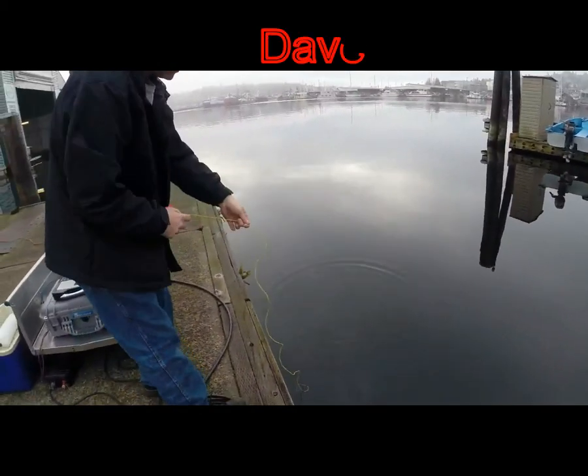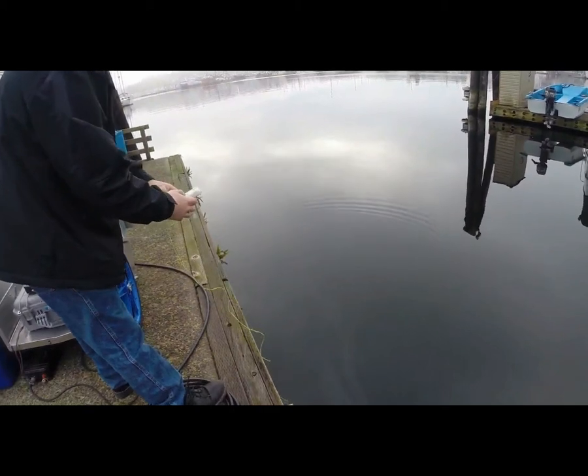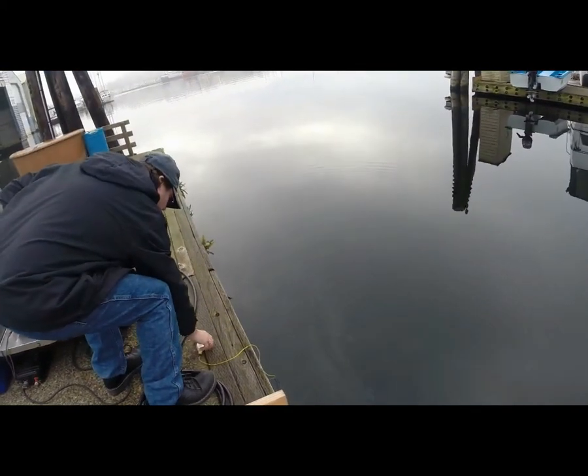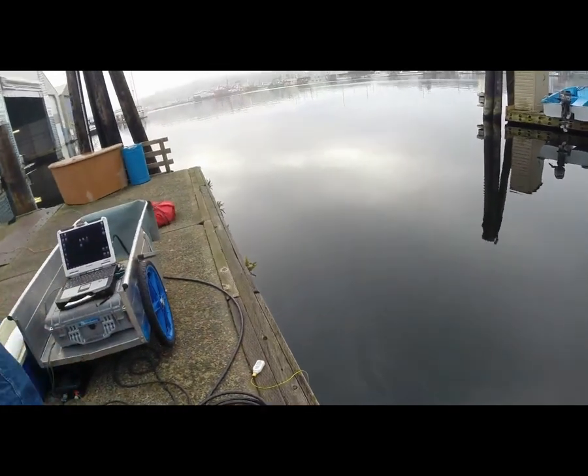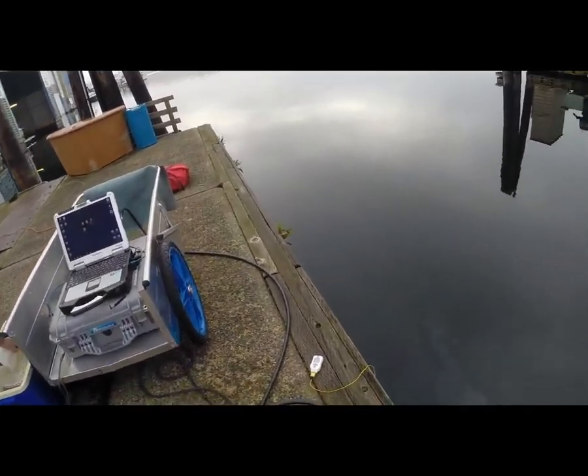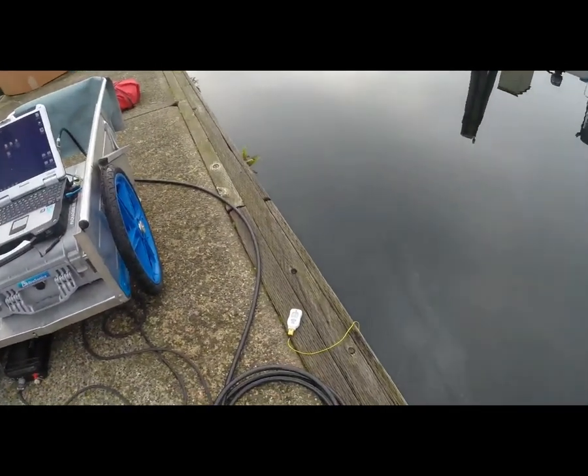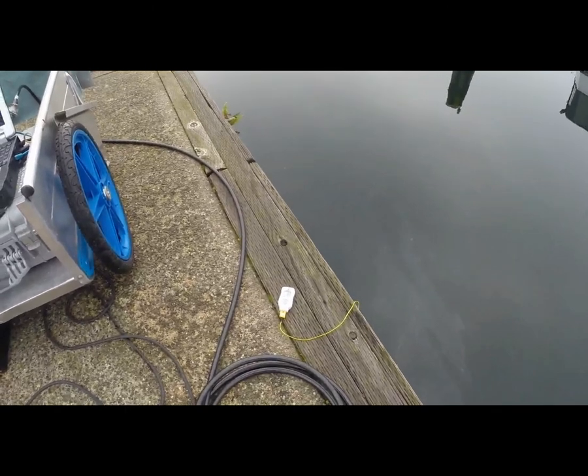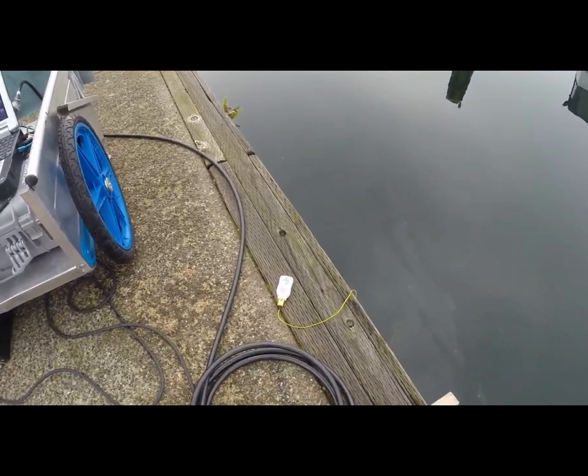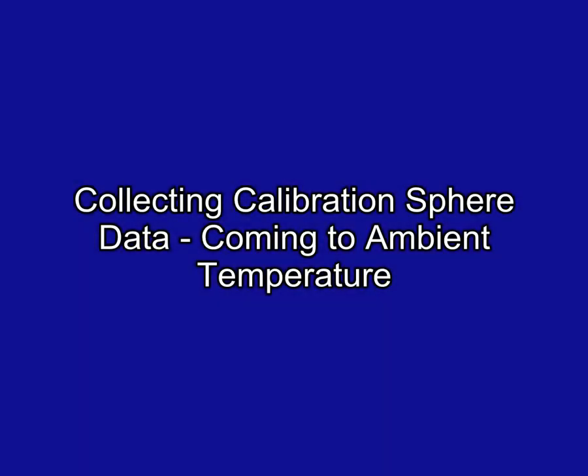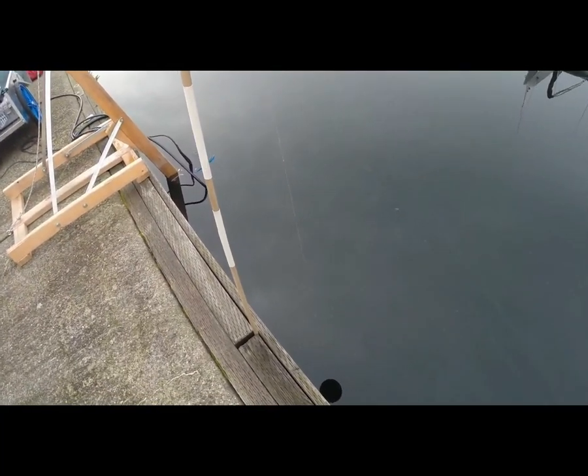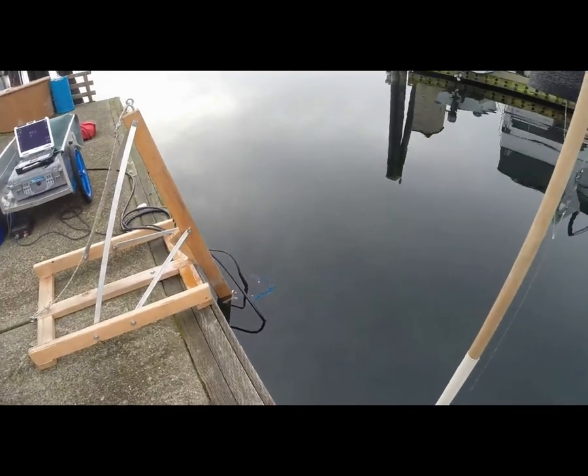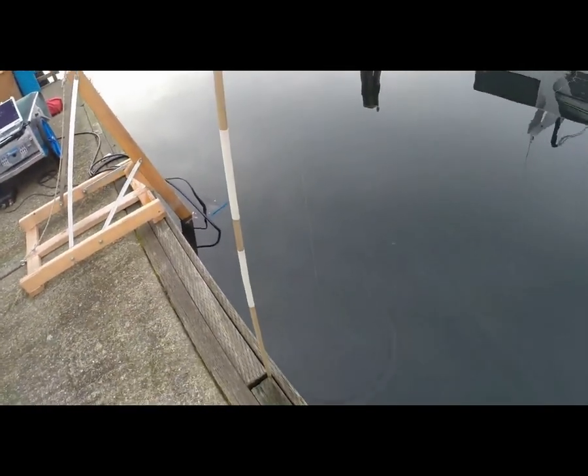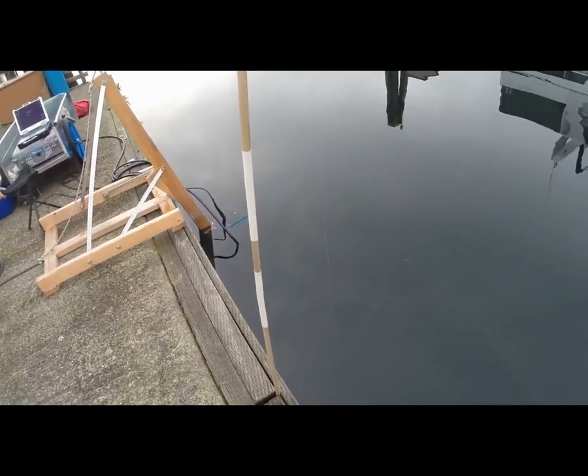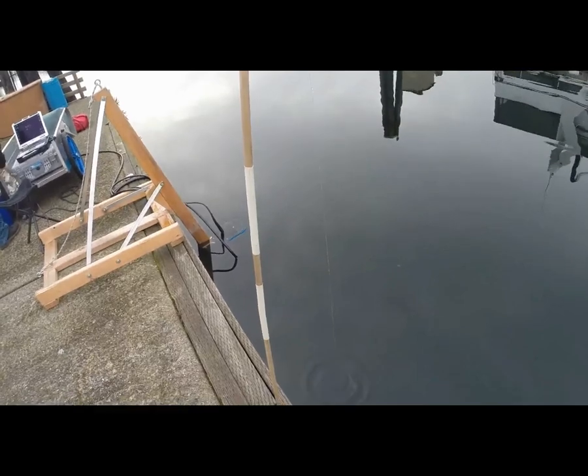So it is important to know the temperature of your water, as well as the salinity if that's a factor if you're not in fresh water. You don't have to be super accurate, but within a degree Celsius would really be nice. And as you can see, we have a nice little thermometer. It's evening out at 8.8 degrees Celsius. Allow both the calibration sphere and the transducer to come to ambient water temperature before collecting data, whether you're doing it for fish, plants, bottom typing, or calibration.